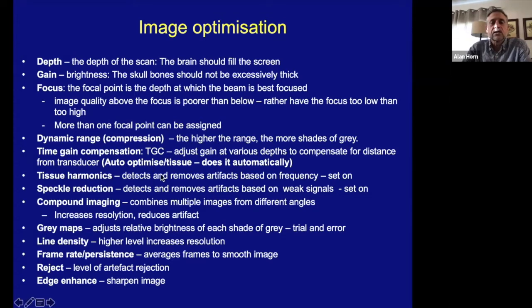Tissue harmonics detects and removes artifacts, and that should generally be on. With all of these, there can be a trial and error, and you can see if it improves the image or not. But in general, I would expect it to improve the image. Speckle reduction similarly removes artifacts. Compound imaging sends multiple beams from different angles to improve the resolution of these artifacts. Gray maps again give you a different brightness of each shade of gray, so it can make the images easier or more accurate.